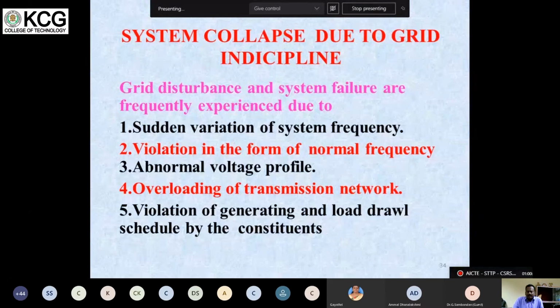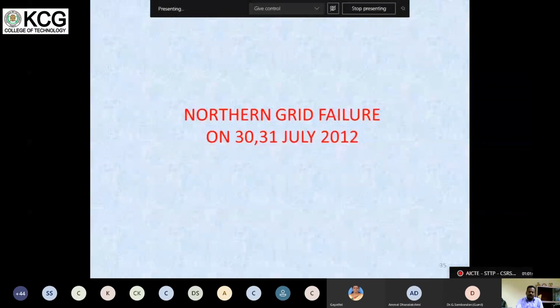And violation of generation and load schedules by the constituents. In the morning we must have discussed this violation of rules. There are states fixed with some entitlement, like now TNEB, or we say TANGEDCO, can draw, say, 250 megawatt from NLC. They should draw only 250 megawatt. If they draw more power, then it leads to problems in the total grid. So violation of generation and load schedules also leads to grid collapse. So grid collapse, one example we will see, already might have discussed, but still we will see.